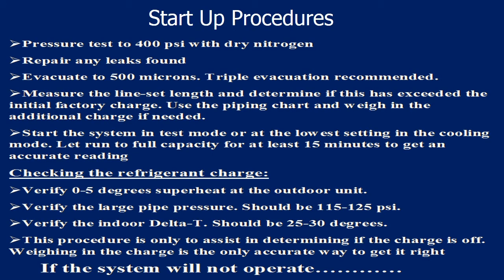Before the system is started up for the first time, the following items should have been completed. A nitrogen pressure test of all the flared connections up to at least 400 PSIG, an evacuation of the refrigerant tubing down to a minimum of 500 microns utilizing a micron gauge to measure the level of the vacuum achieved. Verify the total distance of the refrigerant tubing installed and make any refrigerant charge adjustments based on the refrigerant charging table referenced in the installation manual.